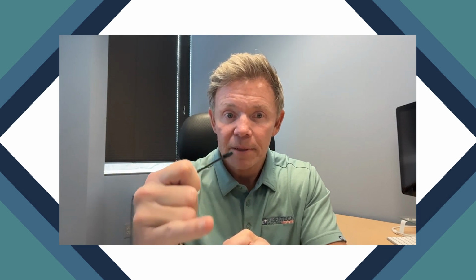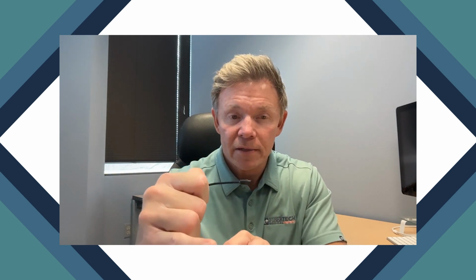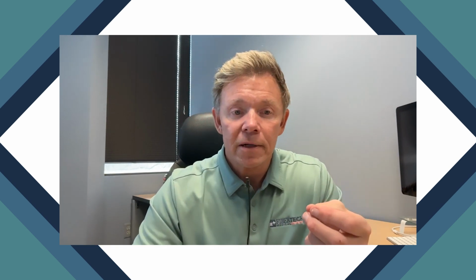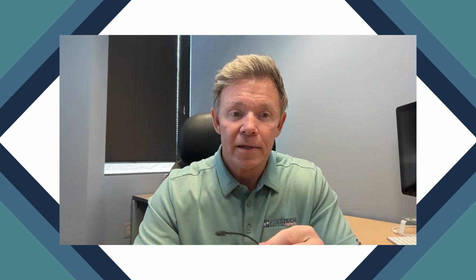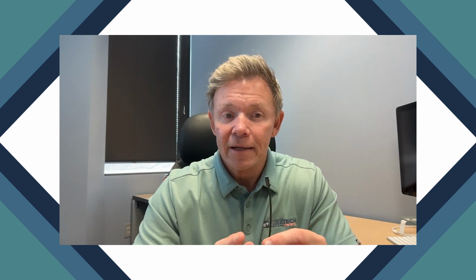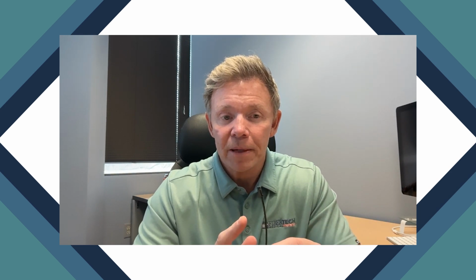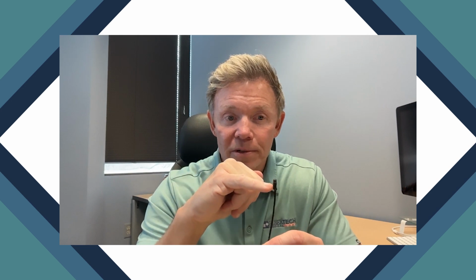If you look at the tip of the scope, you'll see three lenses. The two outer lenses are for light, but the center lens, right behind that center lens on the distal tip of the scope, is where this CCD sits. The camera is encased. It's a fairly robust component. It can take a little bit of being knocked around and swinging around. But again, it's a good time to bring this up, because what damages this the most is getting fluid inside the scope.